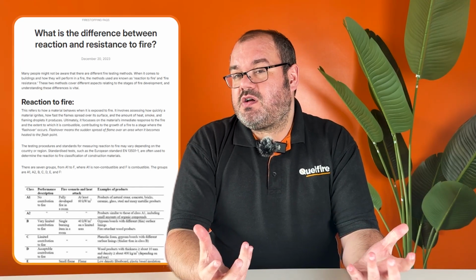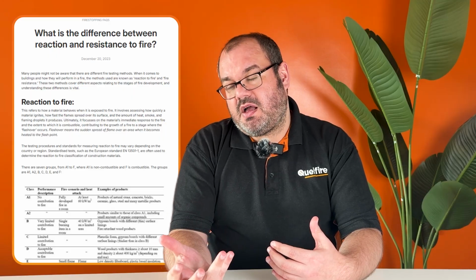So this is important when you're looking at your fire strategy, because your fire strategy should determine what your requirements are. Is it both integrity and insulation, i.e. EI rating, or is it integrity only? And understanding the difference is important, because when you start having large metal services like cable trays, cables, steel sprinkler pipes, those types of things, which again, going back to earlier knowledge hubs where we're talking difference between reaction and resistance, they are non-combustible materials, metal cable tray, a steel pipe, but they generate heat. Metal is a good conductor of heat.